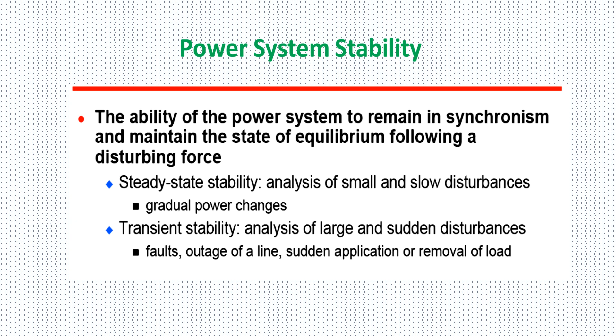Transient stability study deals with the effects of large sudden disturbances such as the occurrence of a fault, particularly a three-phase fault, the sudden outage of a line, the sudden application or removal of load, or tripping of a heavily loaded line. Such studies are conducted when new generating and transmitting facilities are planned. These studies are helpful in determining the nature of the relaying system needed, the critical clearing time for the circuit breakers, the voltage level, and the transfer capability between systems.